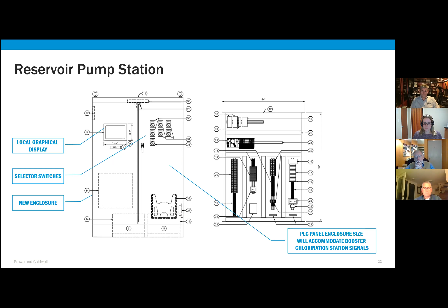So some of the panel features: there'll be a local graphical display at this site. There are some hardwired selector switches that we're maintaining that were on the existing panel. Those are for valve control. It'll be a nice new double door enclosure, plenty of room. The one thing I wanted to mention is that the new booster chlorination station project will be adding additional equipment to this site, and we've designed the panel large enough to accommodate all of that future equipment. So our project will be going in first, and then the booster chlorination station project will be after.